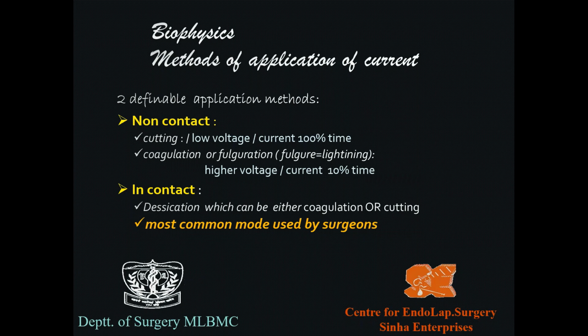So the first is what is known as the non-contact mode, which is a cutting mode where you use a low voltage current 100% of the time. I just now showed you in the last slide. Coagulation or fulguration. Fulguration basically means lightning. Lightning basically means what? Appears and disappears. A sudden flash of lightning that goes off. Similarly, out here in fulguration or coagulation, what is happening? 6% on, 94% off. 6% on and suddenly goes off for 94% of the time. So higher voltage current only for 10% or less.